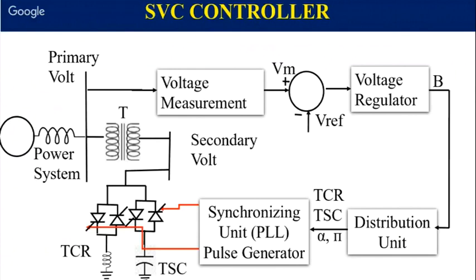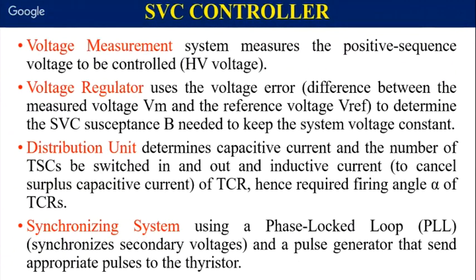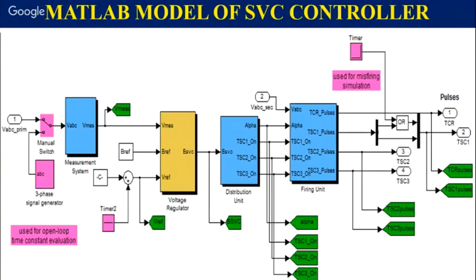You will come to know this when we simulate one circuit. So it is written there, the same things, whatever functions for every block we have discussed. This is the controller in MATLAB. This is already a developed model. Here is the measurement system. Here is the voltage regulator, which calculates the susceptance. Then the susceptance value is given to the distribution unit, which decides which units should be switched on. Accordingly, pulses are generated and given to the capacitor banks, and the firing angle is given to the thyristor controlled reactor.